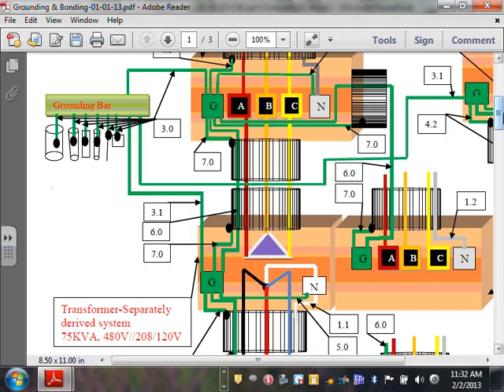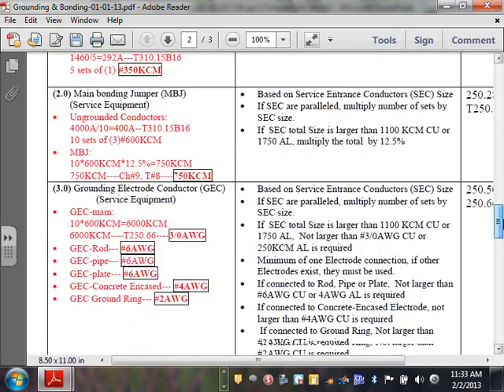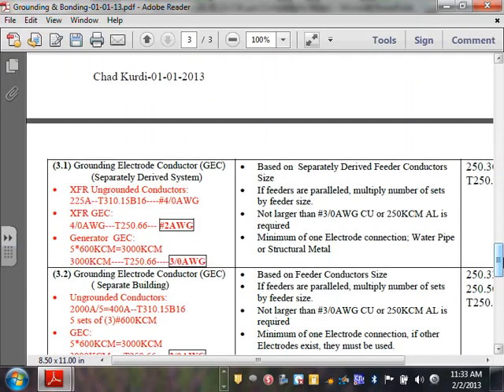Any comments, any questions, guys, about that one? So here's my number 3.1, and I'm going to go to sizing that grounding conductor. If you guys go to 3.1 here, here's my grounding electrode conductor. This time I'm going to use it for the transformer. I have my transformer, I have my panel, I size my conductors. So basically you size it based on the conductors coming out of the transformer.